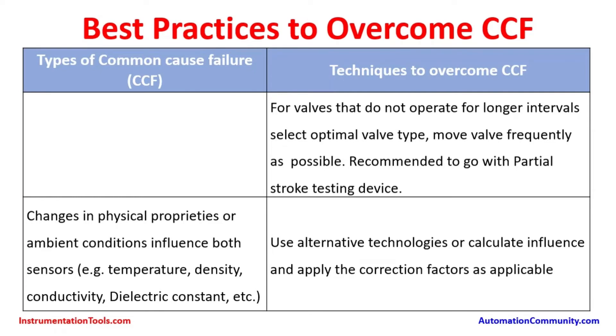Normally, safety instrumented system emergency shutdown valves close only based on demand or hazard conditions. But if valves remain in the same position for years, the valve stem can become sticky and may not be able to close during a real demand. To ensure valves operate during emergencies, test them as frequently as possible per safety system calculations, and additionally install a partial stroke testing device on the on-off valve actuator to move the valve 5–10% from its full motion.